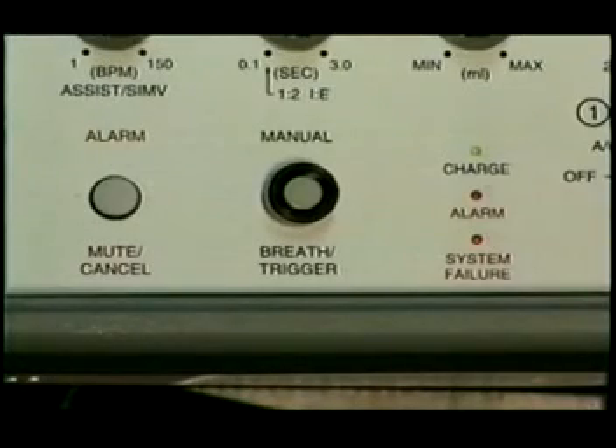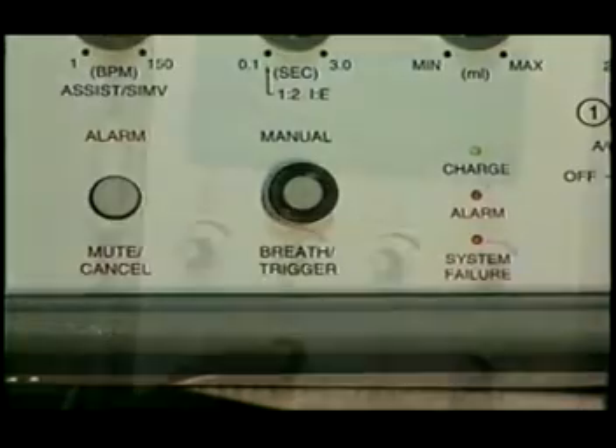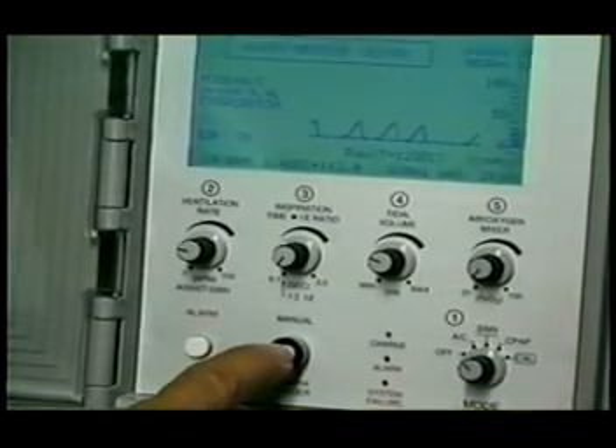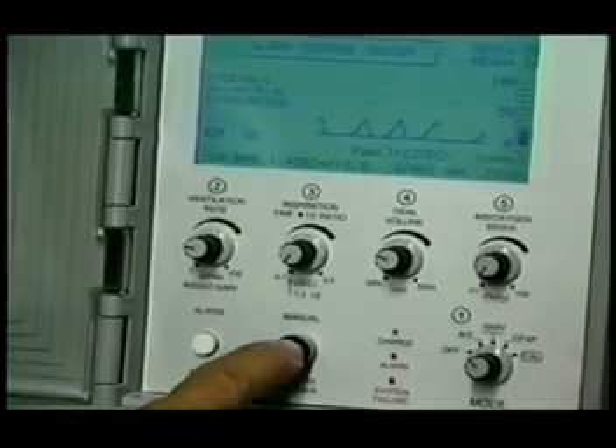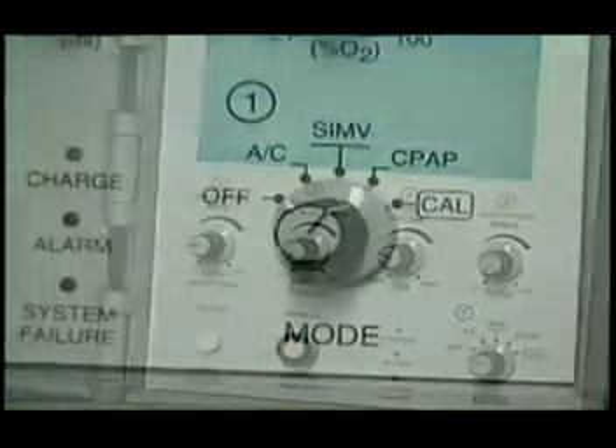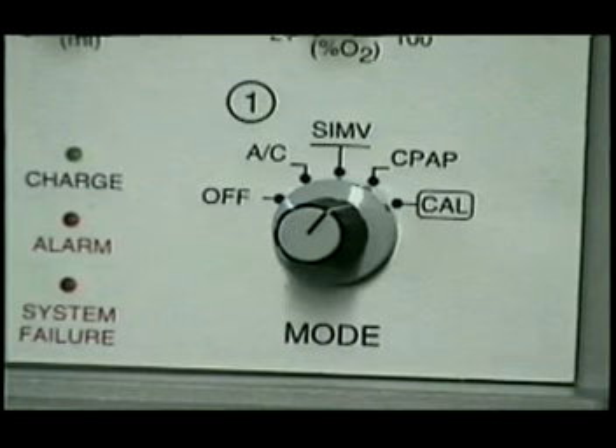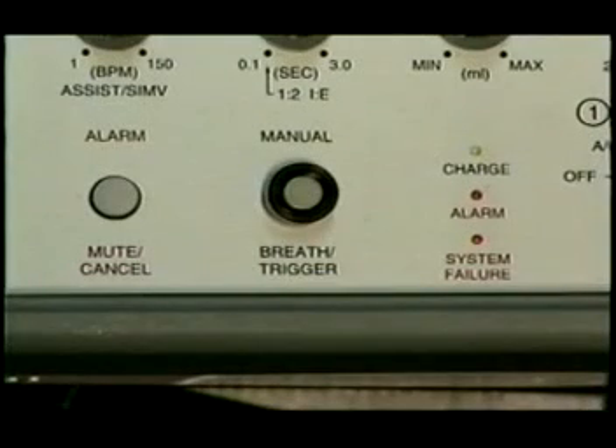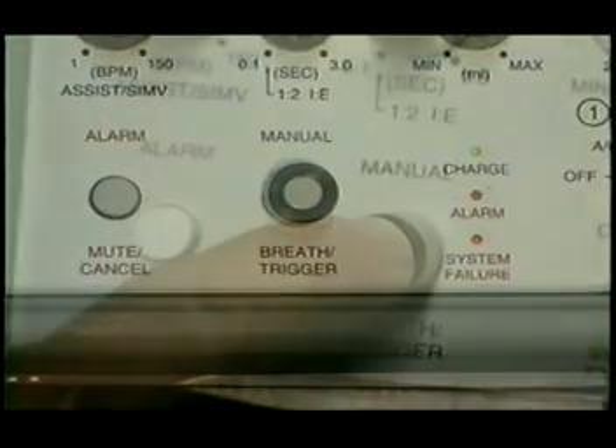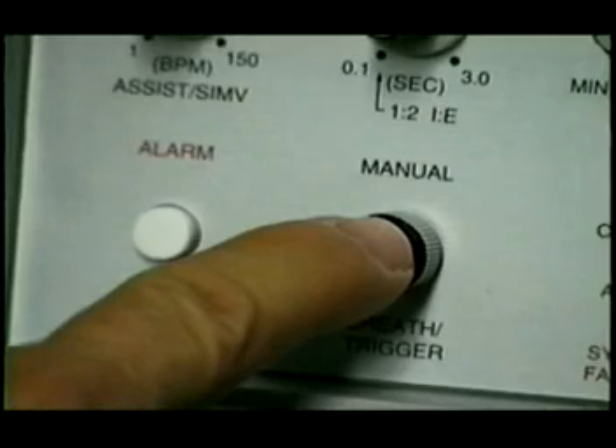The manual breath trigger delivers a manual breath equal to 1 complete ventilatory cycle at current settings in the AC and SIMV modes. In CPAP, the manual breath delivers gas at a 30 LPM flow rate for 1.67 seconds and is pressure limited to 40 centimeters of water. The manual trigger is operational when a system failure has occurred. Gas will flow at a rate of 30 LPM and is pressure limited to 40 centimeters of water for as long as the push-button switch is pressed.